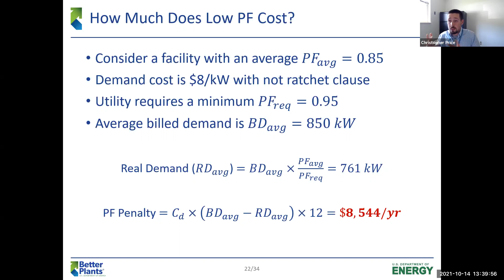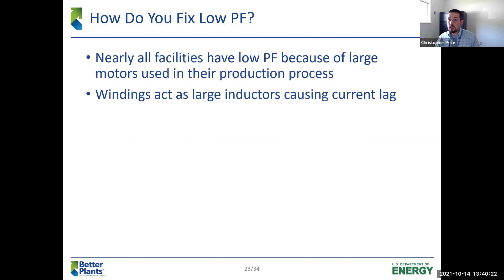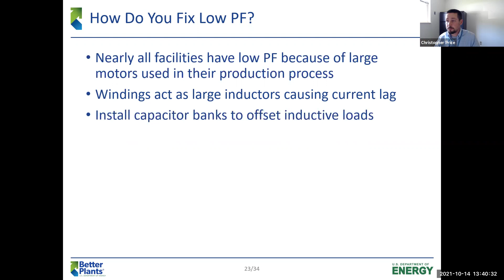So how do you fix a low power factor? Well, nearly all facilities have a low power factor because they have large motors in their facility. Motors are just essentially large coils of wire, which is the definition of an inductor. And inductors cause the current to lag voltage. So the way you would correct this is by installing capacitor banks on site to offset the inductive loads in your plant. There are two kinds of capacitors.